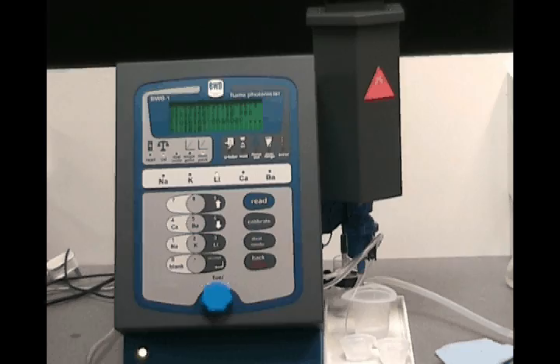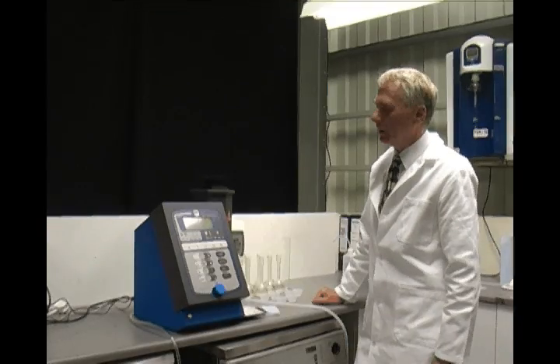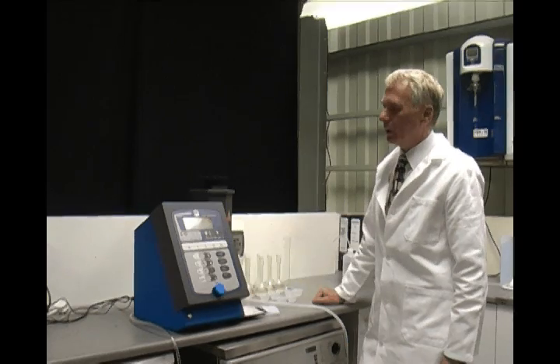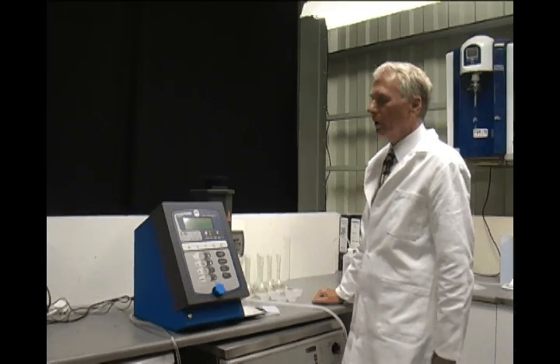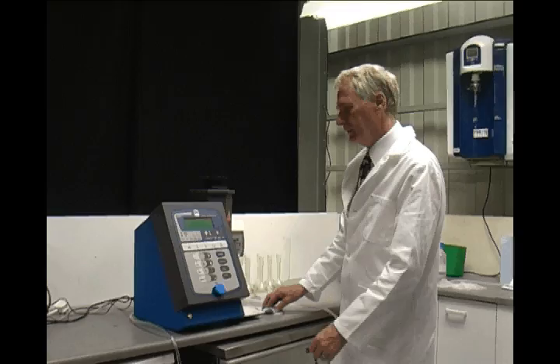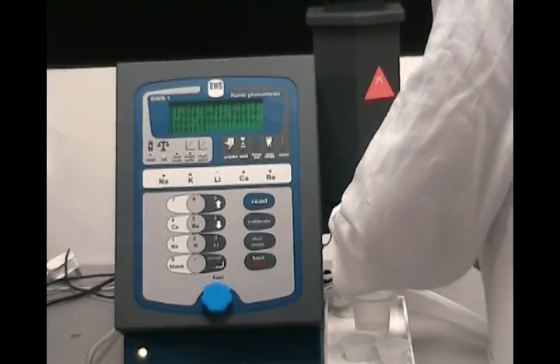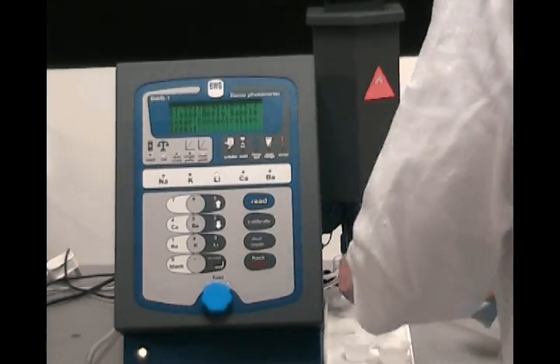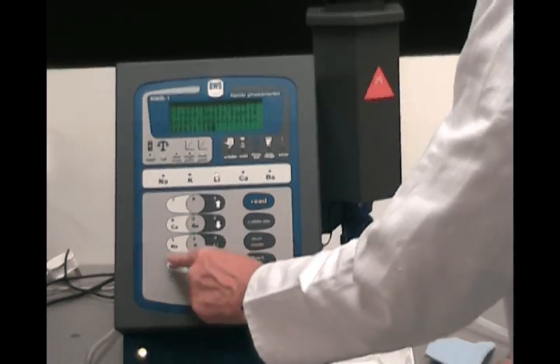You must ensure that when you are moving the aspiration tube from medium to medium, that you clean it and that you don't contaminate your next sample with the sample that you were just using. There we are, that's our 10 ppm calibration. Now to 100 ppm.